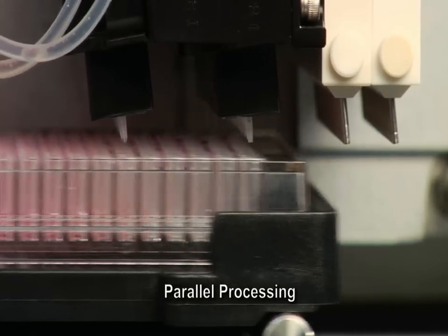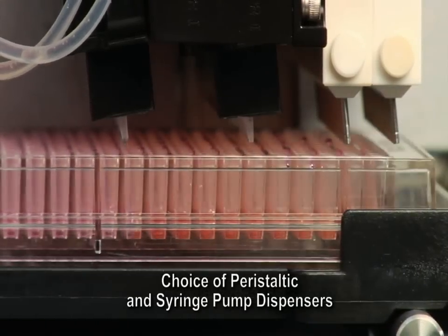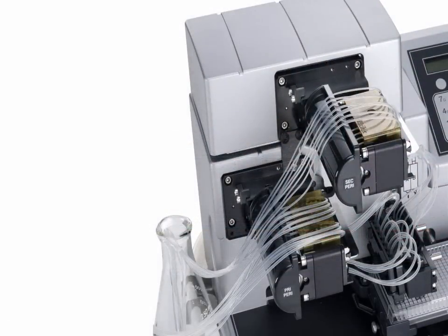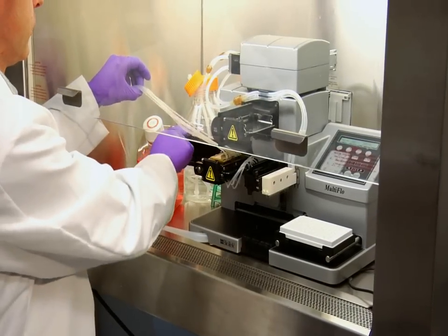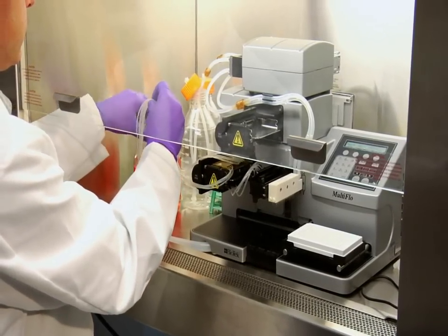The Multi-Flow features BioTek's proprietary parallel dispense technology. A choice of peristaltic or microprocessor-controlled syringe pump technologies are on hand for varying reagent needs. Peristaltic pumps offer low prime volumes and easy back flush capability for unused reagent. Syringe pumps are program-and-forget solutions, offering long-term stability without recalibration and no consumables to budget. With the MultiFlo, a lab can choose instantly whether to use one pump or the other, based on assay conditions and reagent properties.